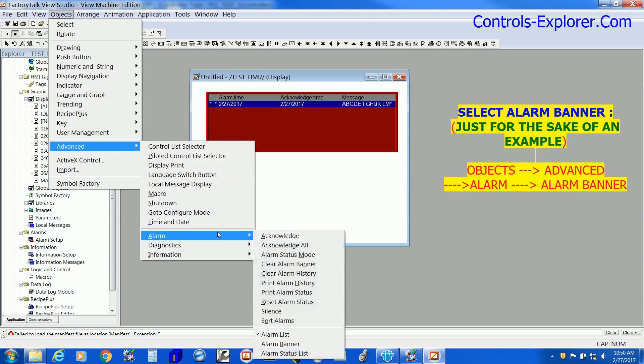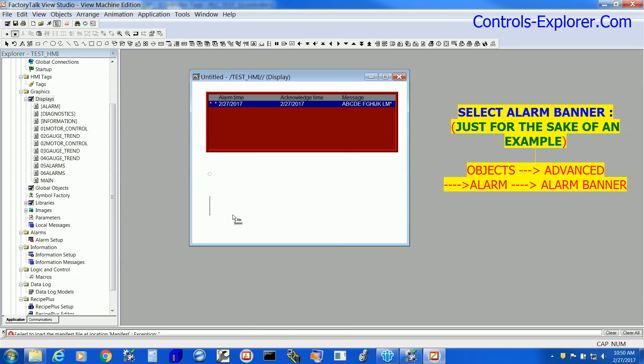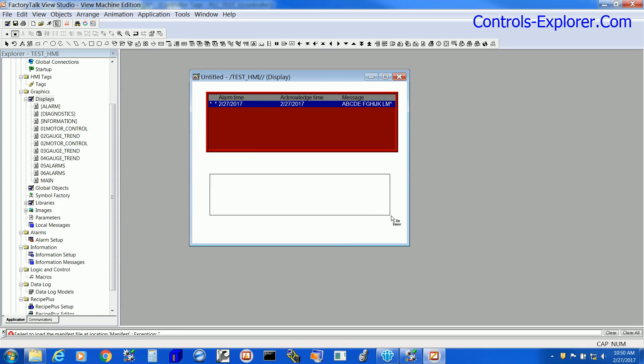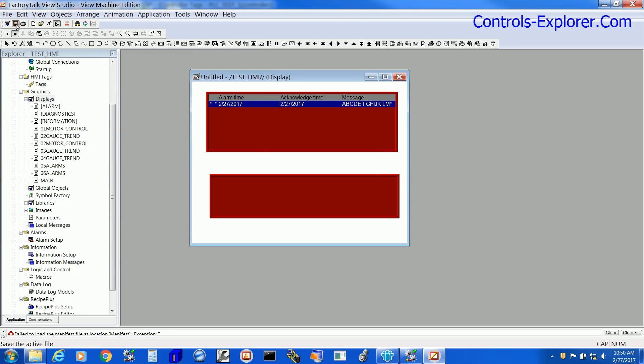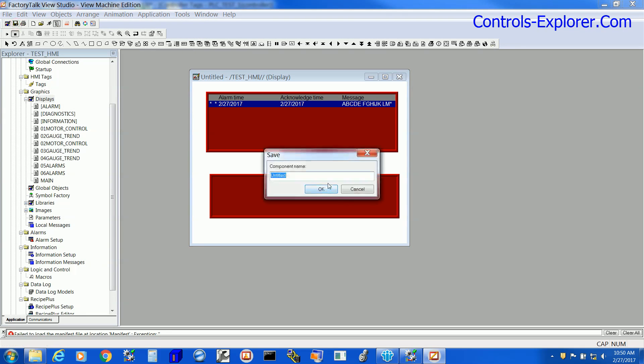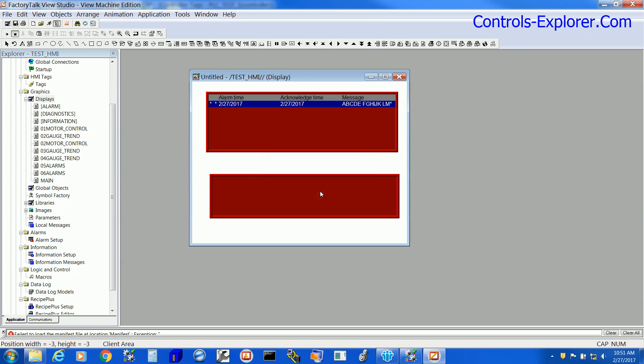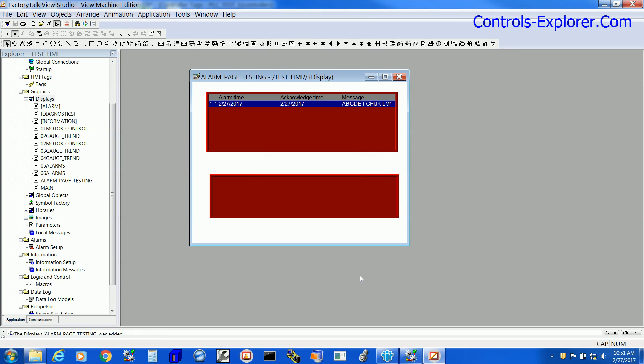Let's go back to the alarm page and this time insert an Alarm Banner. Again, we are not doing anything with the properties window. Save the project and give it a name. This is the way we create alarms in an HMI like Panel View Plus from Allen Bradley. Keep one thing in mind: the Alarm List and Alarm Banner — please do not keep them on the same page. This is shown here just for the sake of example.